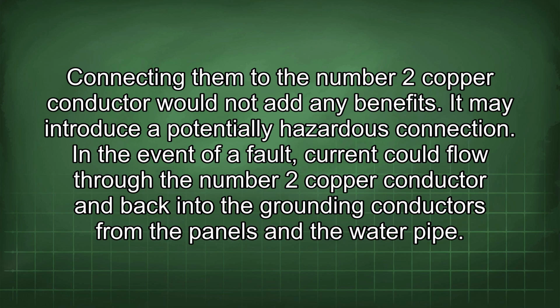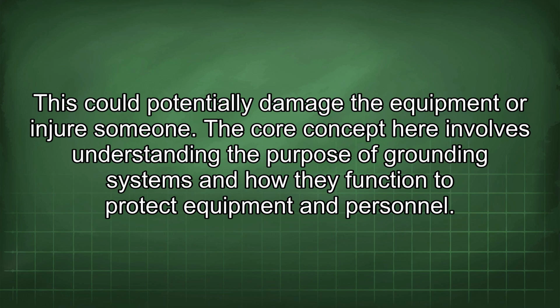It may introduce a potentially hazardous connection. In the event of a fault, current could flow through the number 2 copper conductor and back into the grounding conductors from the panels and the water pipe. This could potentially damage the equipment or injure someone.